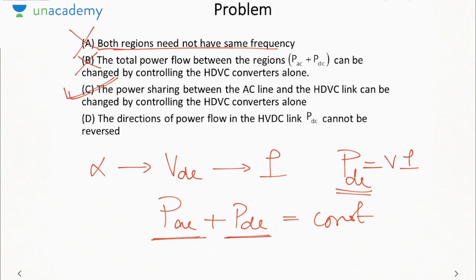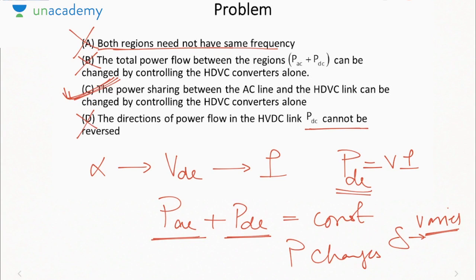How does PAC automatically change? Because if power changes, the power angle delta automatically varies. Okay, power angle is not in our control. As your power requirement will vary, delta will automatically adjust itself. The direction of power flow cannot be reversed. In the previous example just now we saw direction of power flow can be reversed. Hence the C option is correct.